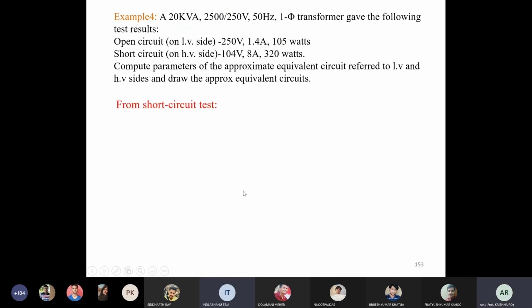So the short circuit test is performed applying 104 volt, 8 ampere, and 320 watt. So 104 is the applied voltage, that is VSC. ISC is the short circuit current or the rated current. Okay, and PSC, that is the copper loss, is 320. Now one thing you have to check, this ISC, if it is the rated current or not. Okay, so you have to check this. So how to check it?